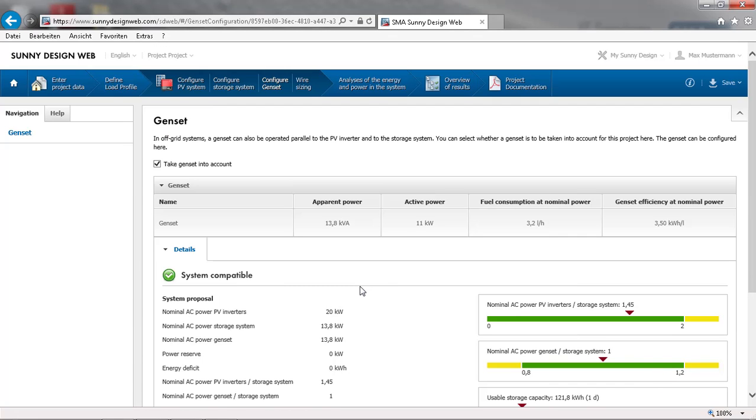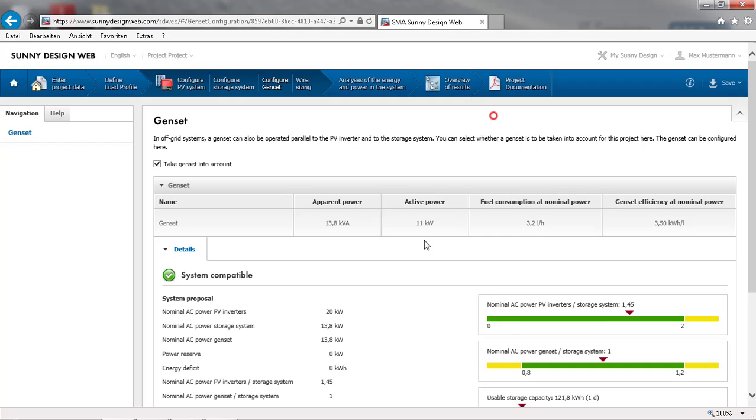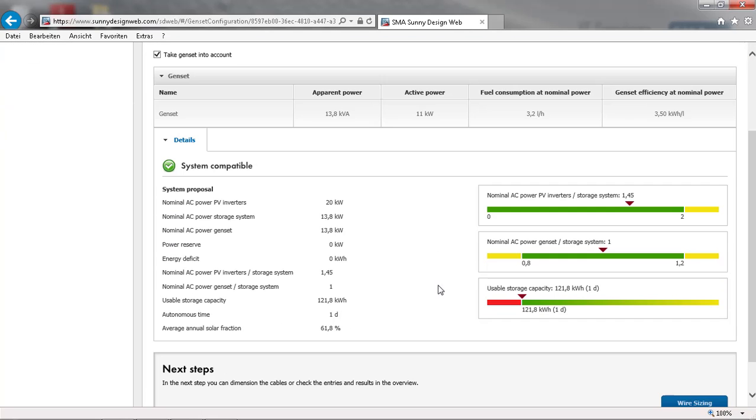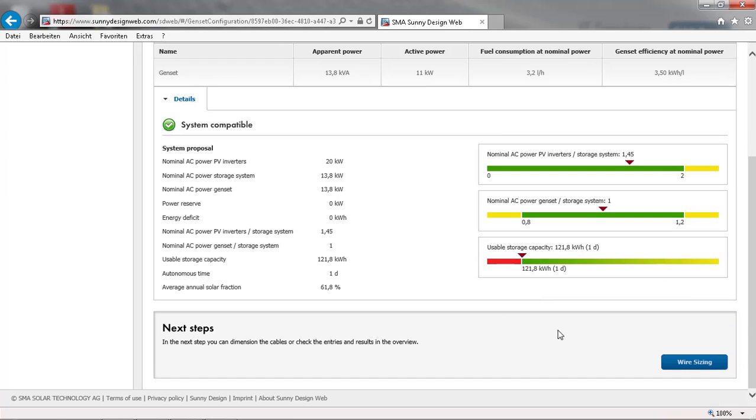In many off-grid systems, a diesel genset is already on site. If this is the case, we have to enter the settings of the genset regarding apparent power and active power. Once this is done and the system is within the ranges, we can proceed to the wiring sizing.